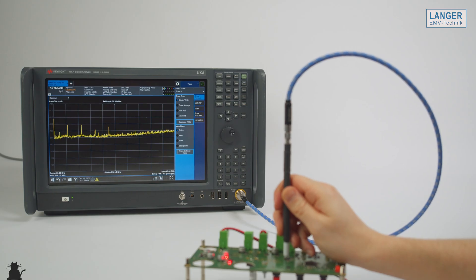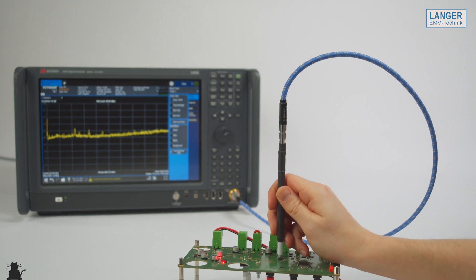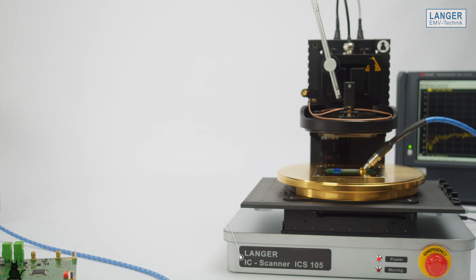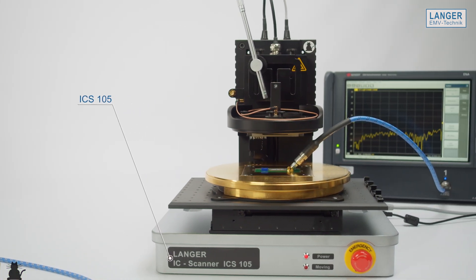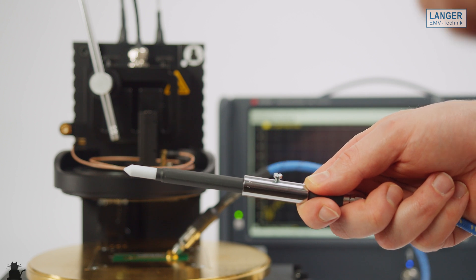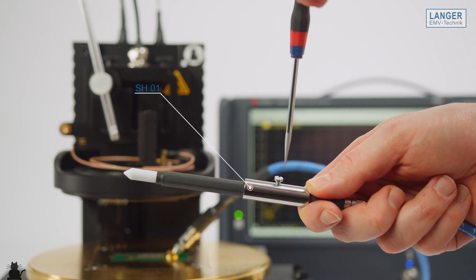For spatially reproducible and reliable measurements, it is recommended to use the probe in an automatic positioning system, for example in a Langer scanner. The probe must be used in the scanner with the SH-01 probe holder.